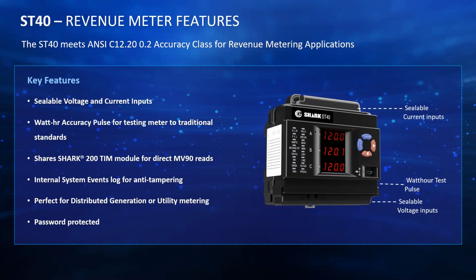Internally, we also have anti-tampering measures where we have a system events log. This records any type of administrative change that was made to the meter, whether someone changed the time, the programming, reset energy or demand values. All of that gets recorded in a system events log, which is not clearable. No matter whether you have full access to the meter, you cannot erase that log.